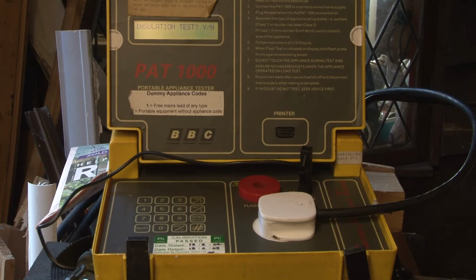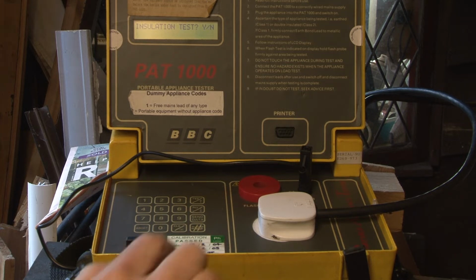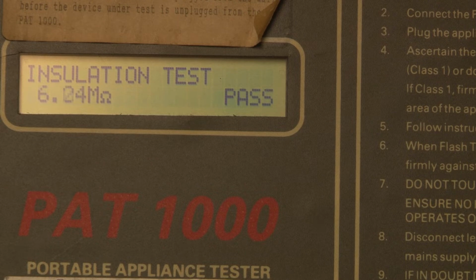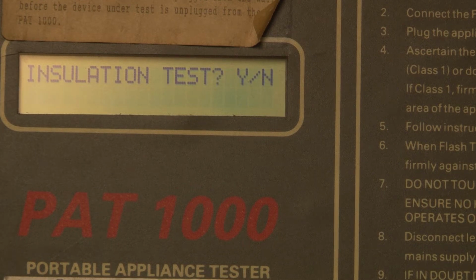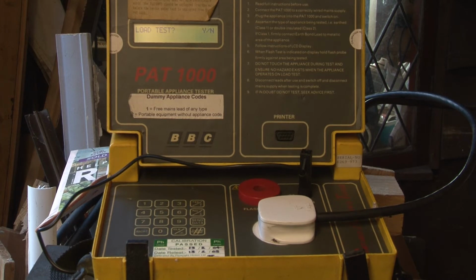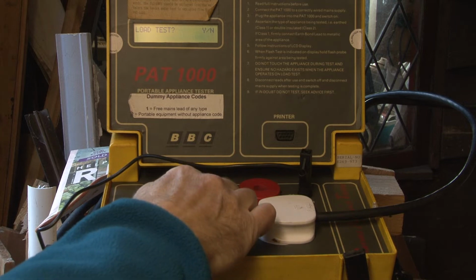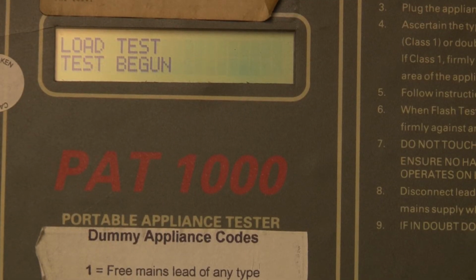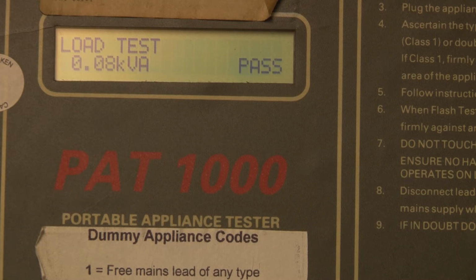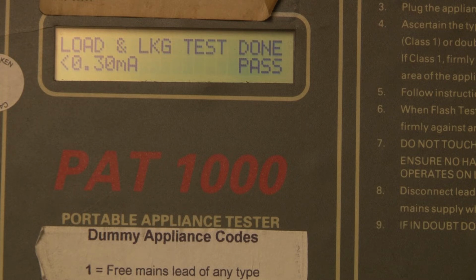Now for the insulation test, what that's going to do is it's going to join the line and neutral conductors together and put around about 500 volts on those, and measure if there's any leakage through to the earth conductor. So we'll go ahead and do that test now. And finally the tester will do a load test. It's basically just going to switch the unit on for a few seconds. Again, it's happy with those results.